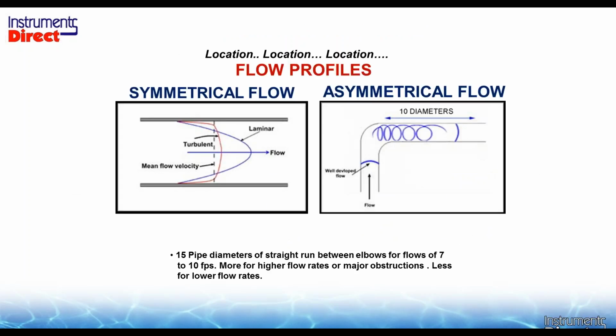Second, some people think ultrasonic flow meters are magic and work everywhere, but they have a limited specification just like every other flow meter technology. In this case, it needs a straight run of pipe. Everybody's flow meter needs a straight run of pipe. We need the traditional 15 pipe diameters for flow rates between 7 and 10 feet per second. If you were to size a pipe and put a pump in there, you traditionally size it for around 7 feet per second. So that's what the 15 pipe diameters are.